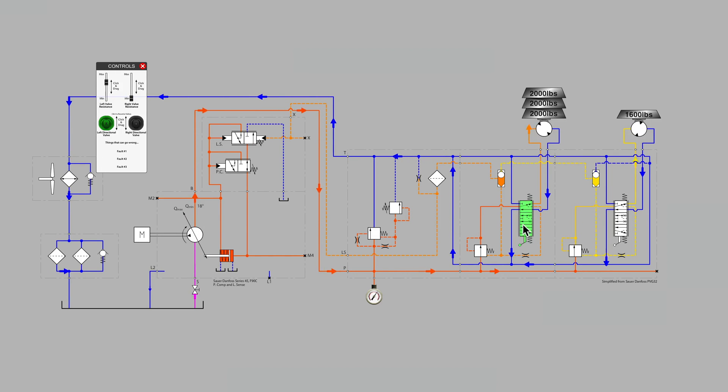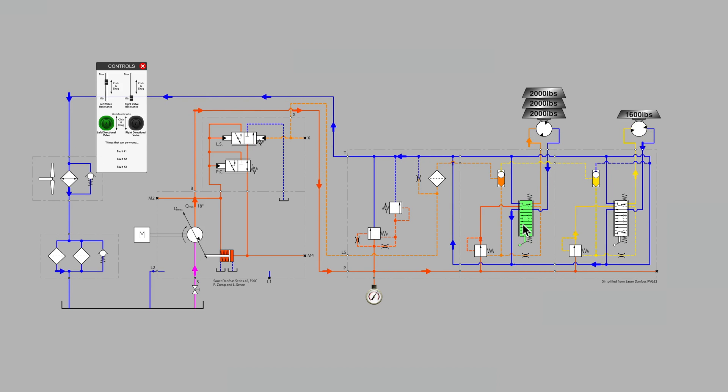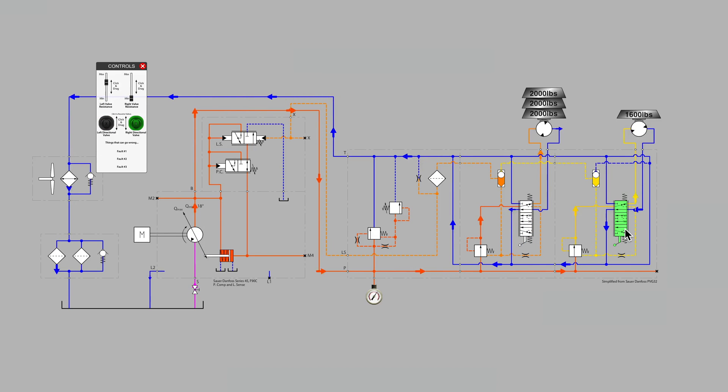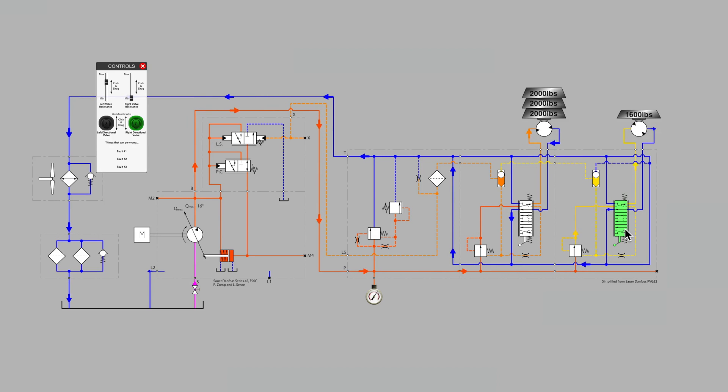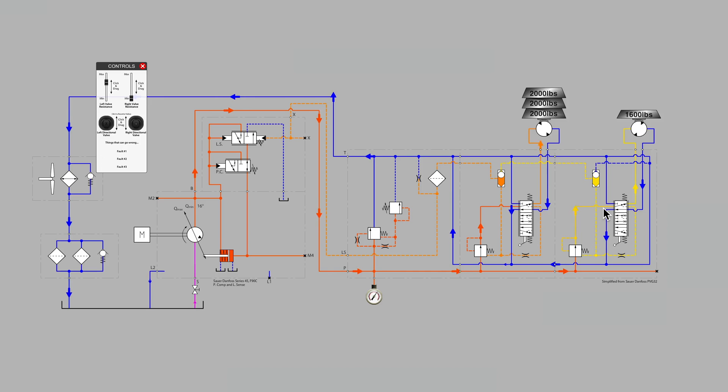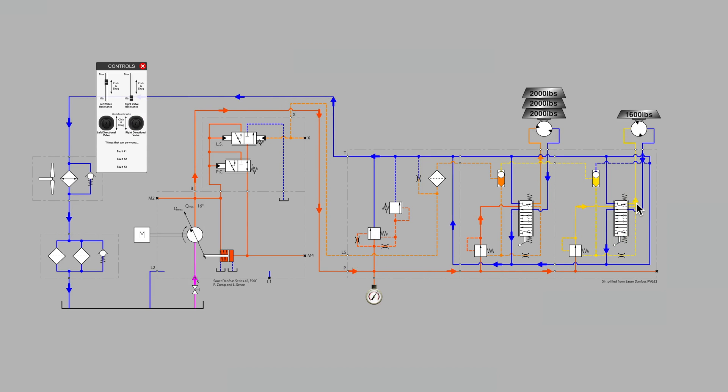the flow rate through a directional control valve, which is what this first spool section symbol means, and the second section spool, the flow rate through that valve is largely a function of the pressure drop from the inlet side of the spool to the outlet side of the spool.